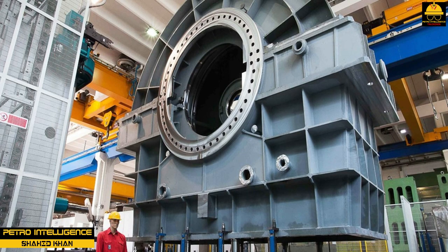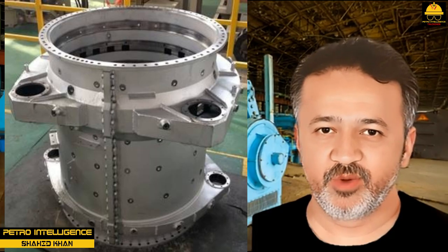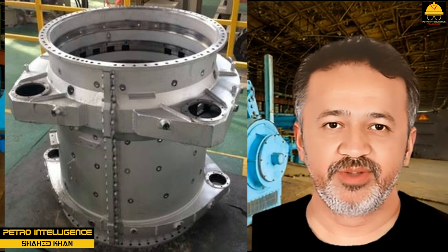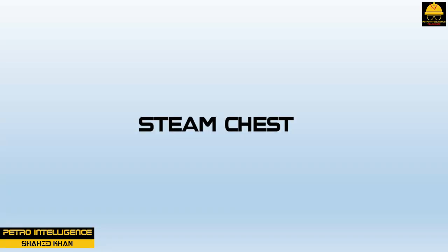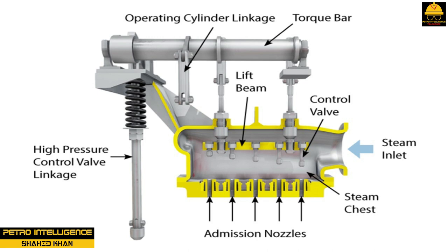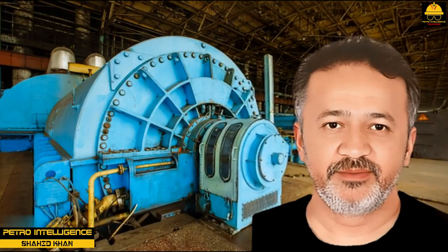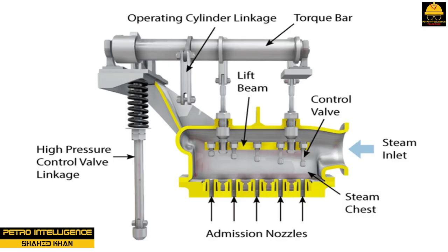The casing is composed of a base and covering made of carbon steel or turbine iron; the base and covering are designed to form steam-tight joints, and gaskets typically are not needed when reinforced flanges are used. The steam chest houses the governor valve, overspeed trip, and steam strainer — a mechanical device that removes impurities from steam — composed of carbon steel or iron and bolted to the lower casing. The nozzles and nozzle block constitute a precision instrument fabricated from a solid block of high tensile carbon silicon steel that directs high velocity steam against the rotor. Nozzle blocks are bolted to the steam chest, and the nozzle has overlapping exits that allow steam jets to converge before being directed against the buckets of the rotor.